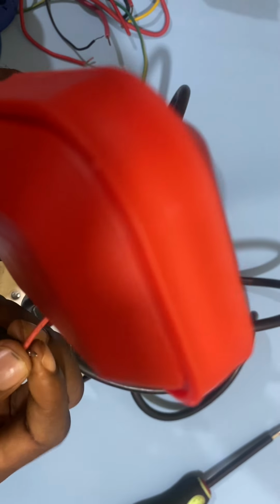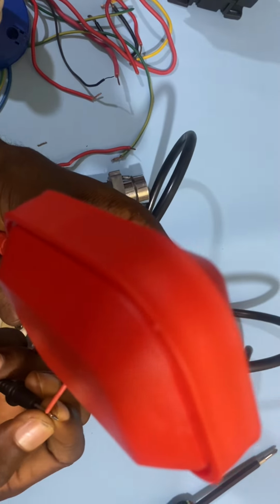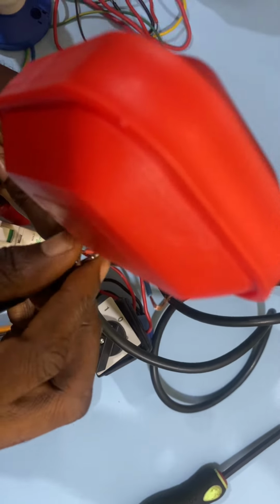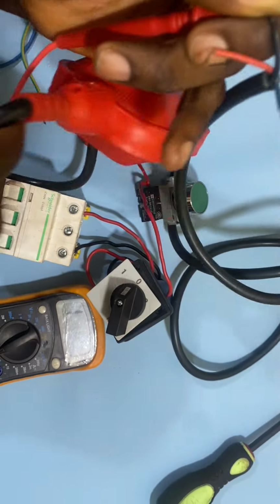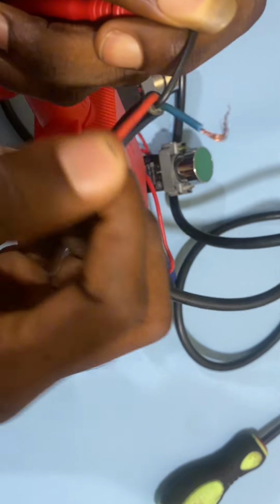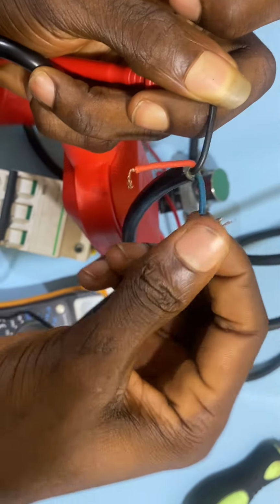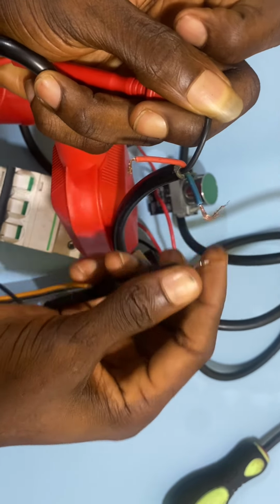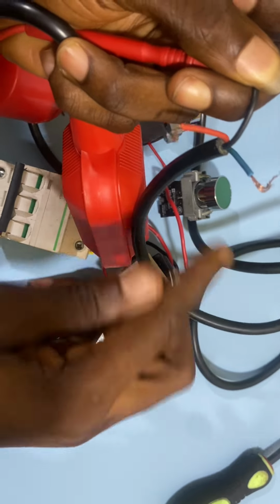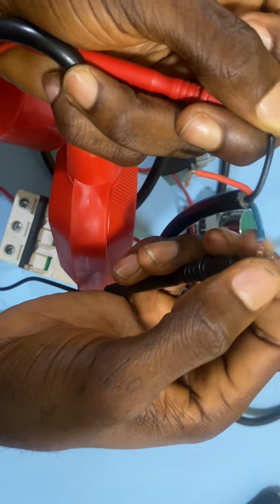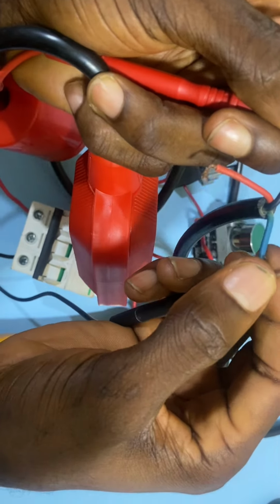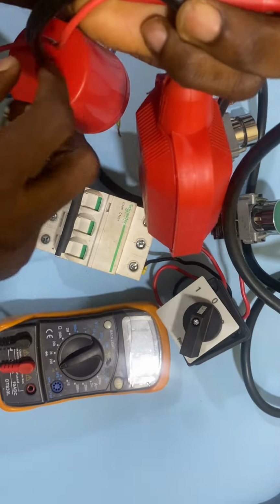So it's at this position, up, facing up. Here, the red is normally closed and the blue is normally open, meaning that the water has filled the tank. But when it's down, here is now normally open and the blue is now normally closed. So therefore, we want the water to start pumping when the knob is facing down. So that means that we are going to use the normally open terminal of the flow switch to do the connection. So let's do that.